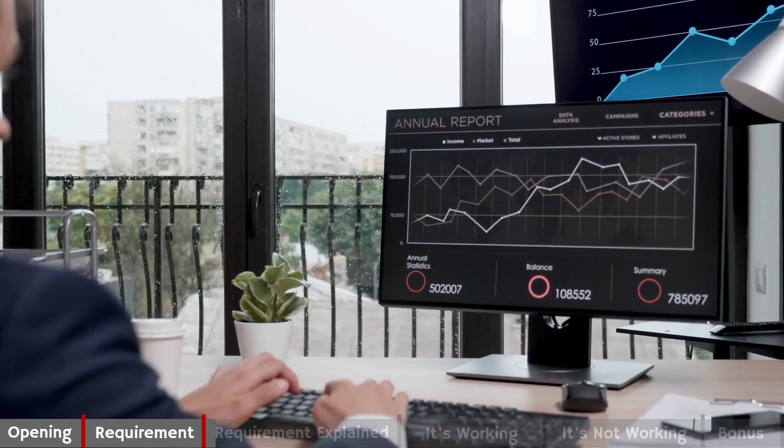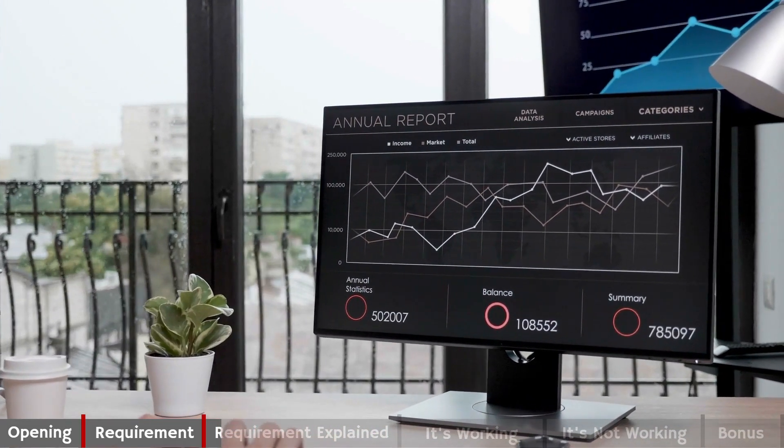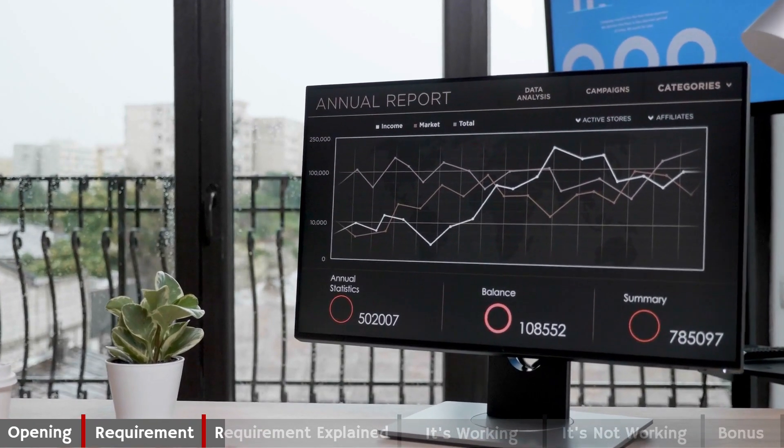The use of statistics is an integral part of any process validation. We utilize statistics for in-process controls and checks, final release inspection — the sampling we do on final product — the number, length, and duration of our OQ runs, the number of PQ runs, the extent of software testing in IQ, OQ, and PQ, and any process capability analysis that we do.